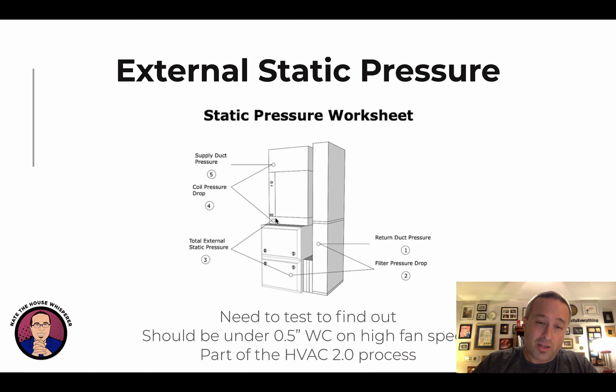Total external static pressure on a furnace is measured from before the fan, since the fan's in here, the heat exchanger's here, and then you test after the heat exchanger. So you're testing before the fan and after the heat exchanger, and the difference between those is your external static pressure. This is part of the HVAC 2.0 process. You're going to get tired of me saying that, but we built this to be friendly to electrification. So you want to find one of these contractors, or create one, which we'll get to at the end of this course.